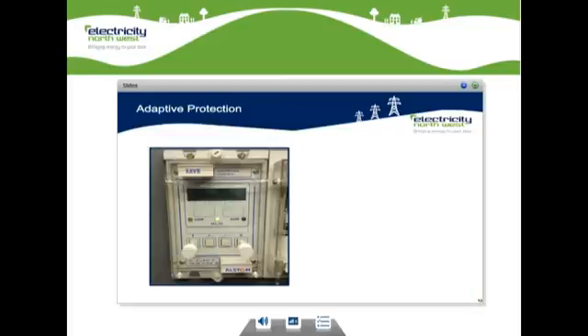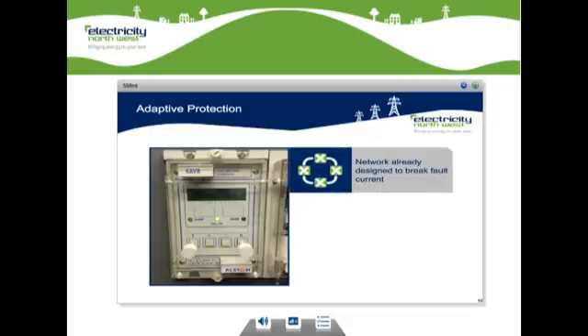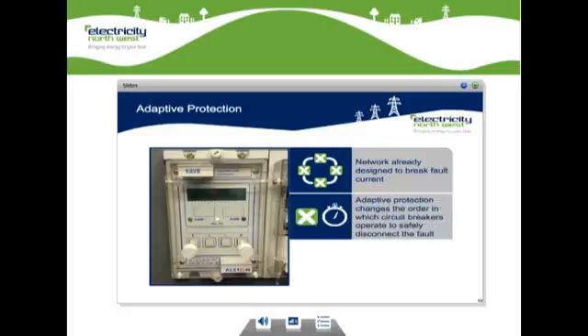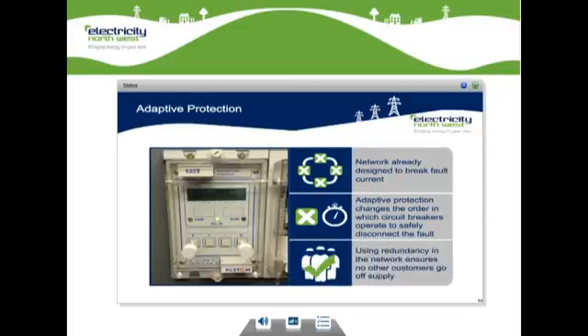The first technique we're going to cover is adaptive protection, also known as sequential tripping. As I mentioned, our network is already designed to break fault current and isolate the fault section of the network using circuit breakers and other protective devices. Adaptive protection changes the order that the circuit breakers operate to safely disconnect the fault from the rest of the network. And by using the redundancy built into the network, we can ensure that using this approach, no other customers will go off supply as part of the change.